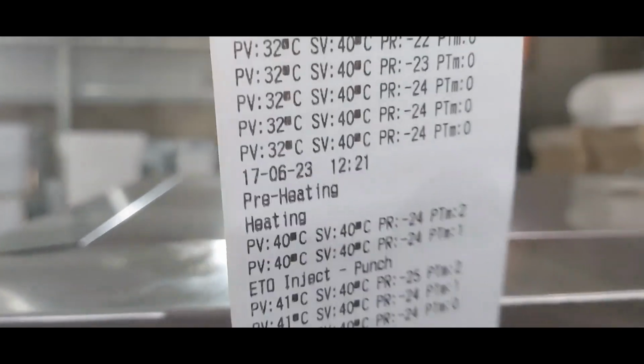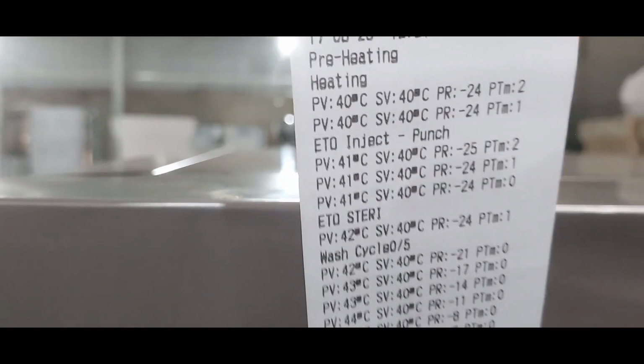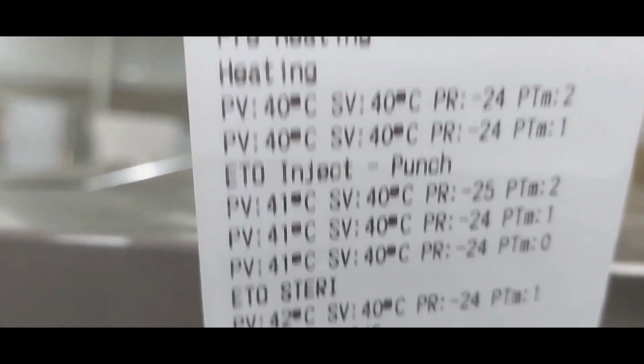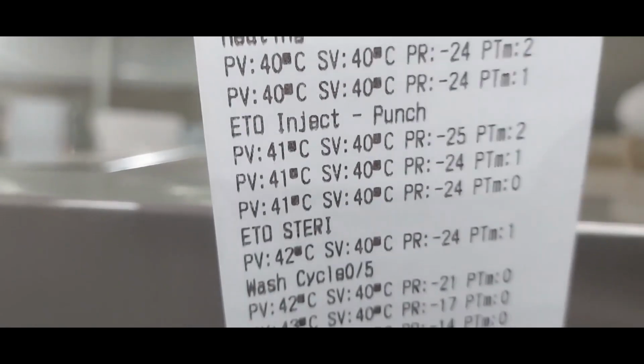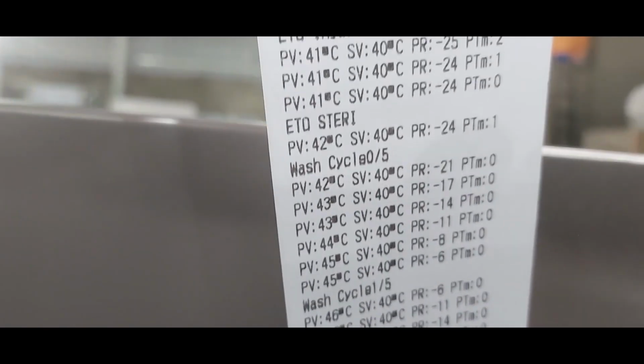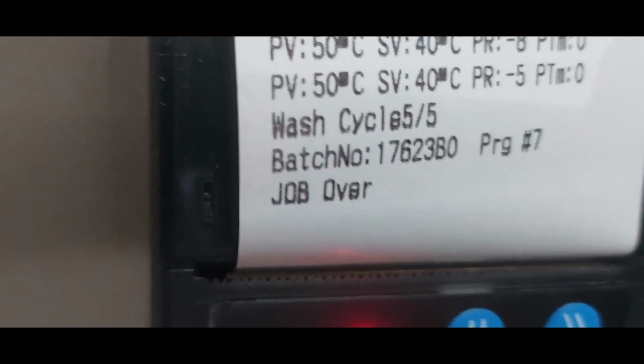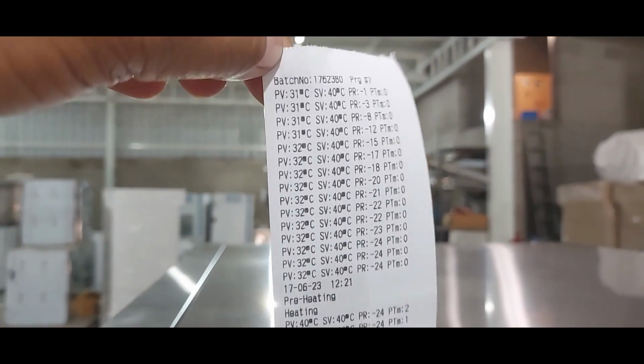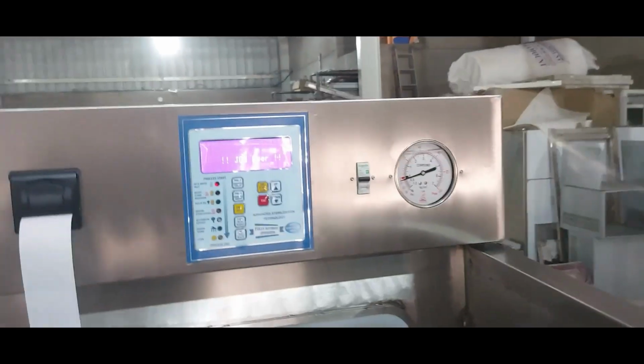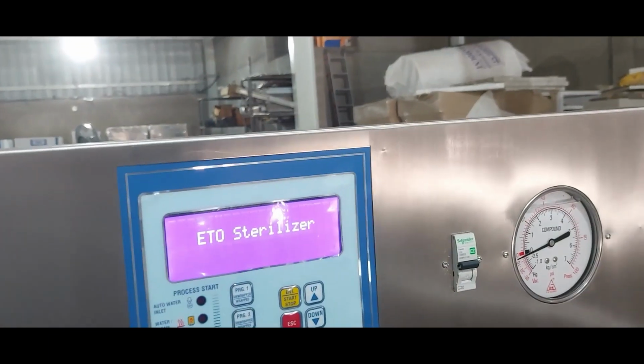Process temperature. First it starts from 0 and goes up to 25 psi pressure. Then ETO inject punch. The ETO inject punch runs multiple cycles, and it takes time to punch and puncture the whole tube successfully. Then ETO sterilization. I have set only 1 minute of ETO sterilization, so one cycle has been displayed. After that, wash cycles 1, 2, 3, 4, 5. The 5 cycles in sterilization are over, and then the last is job over, which gives you the complete batch number on the products. So this is all about the output from the document, and you can keep it for the record. Once you restart the machine, just press the escape button and the ETO sterilization will come back to normal.